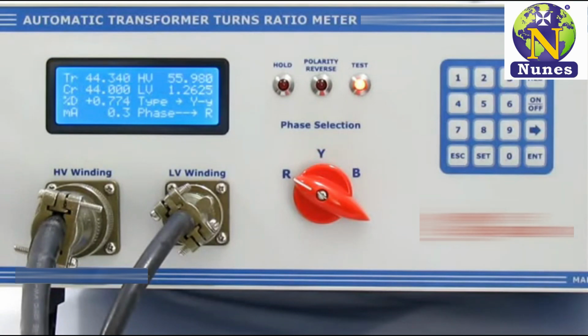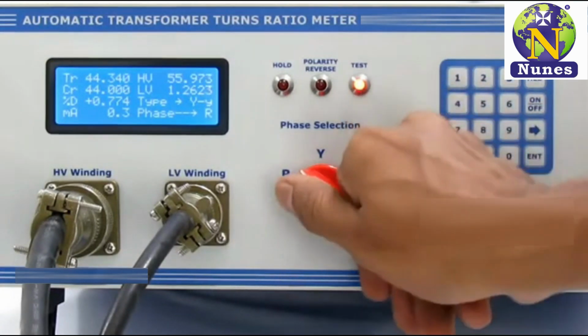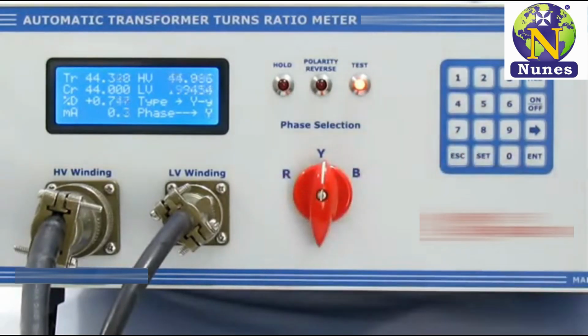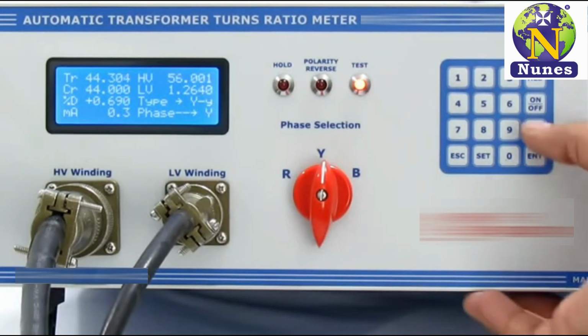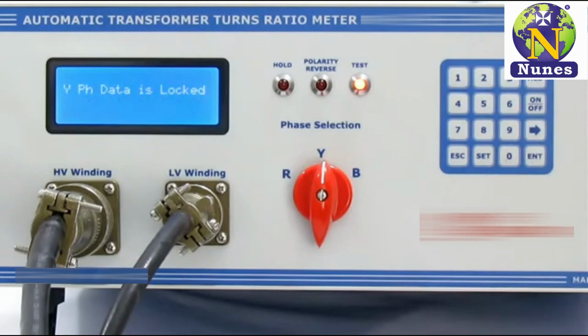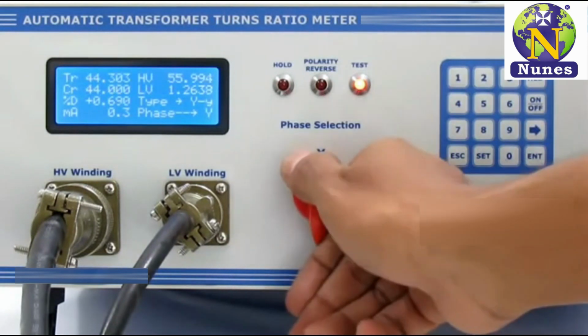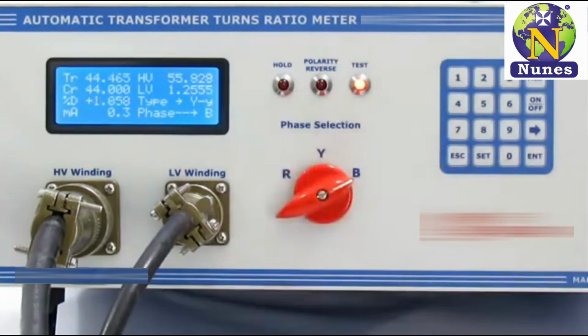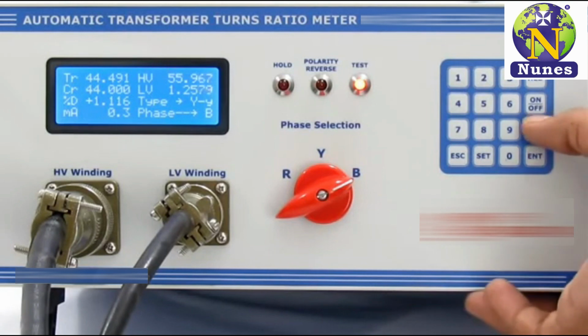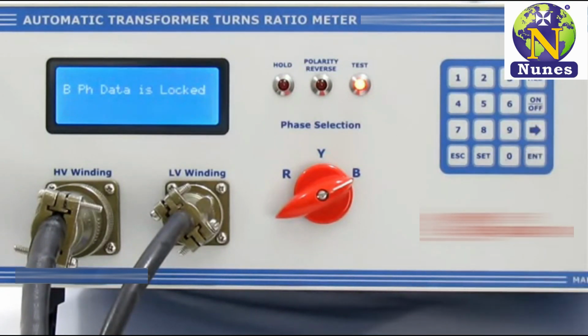Now move this selector switch to Y phase to measure turns ratio of that phase. After seeing stable turns ratio and other parameters, you can press the arrow key to log Y phase's results. Same way, move this selector switch to B phase to measure turns ratio of that phase. After seeing stable turns ratio and other parameters, you can press the arrow key to log B phase's results.